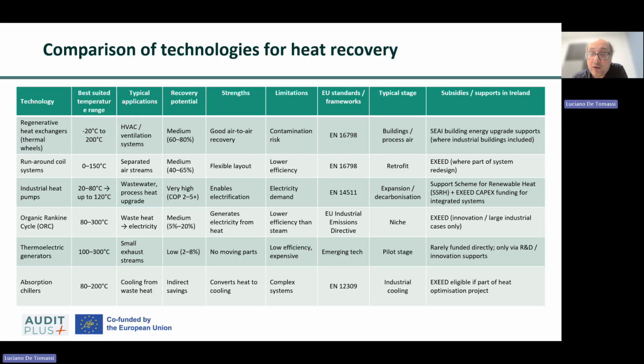They typically recover low-grade waste heat at temperatures between 20 and 100 Celsius degrees and upgrade it to useful process temperatures ranging from 60 to higher temperatures depending on the technology. They are commonly deployed in food processing, dairies, pharmaceuticals, chemicals, and district heating systems. Rather than measuring recovery efficiency directly, performance is usually expressed through a coefficient of performance, which commonly ranges from 2 to 6.